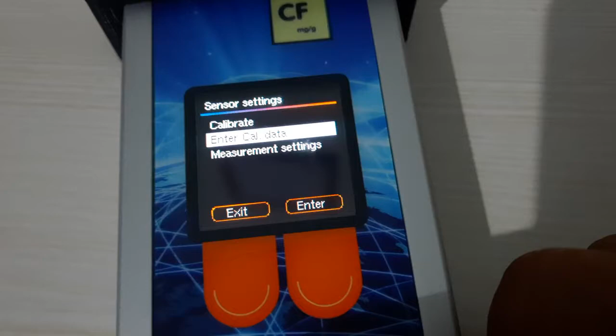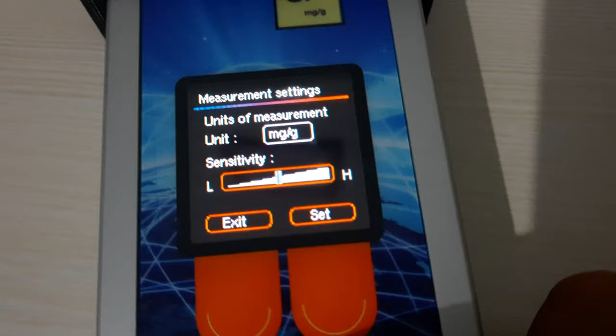go into the measurement settings, enter. It will ask for mg per gram, and also for the sensitivity. So counts or mg per gram, it will ask. Let us put it as mg per gram, and for the sensitivity we can reduce it to medium. This will give you more accurate values. Now I will set it. Now exit. Again, if we measure, it is coming at minus 0.004.